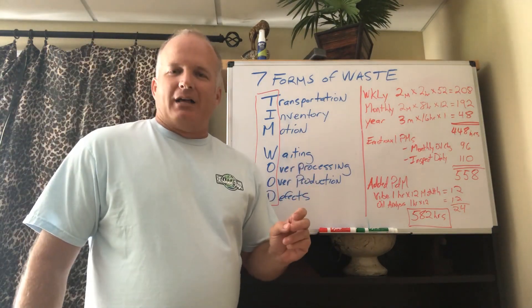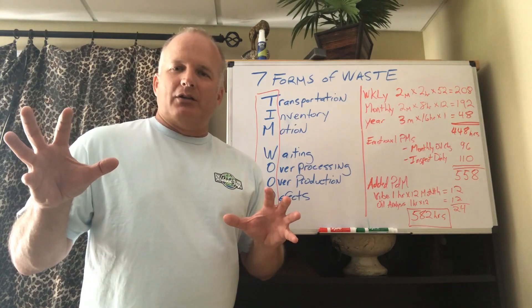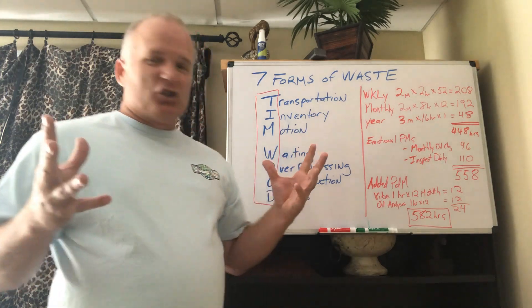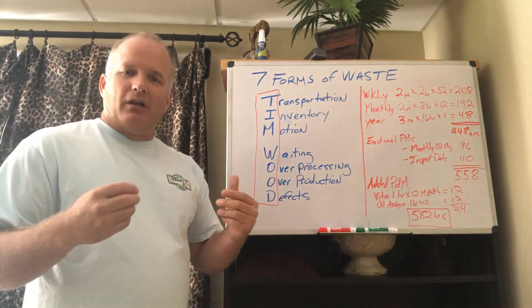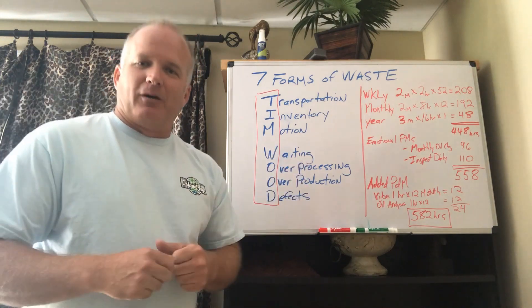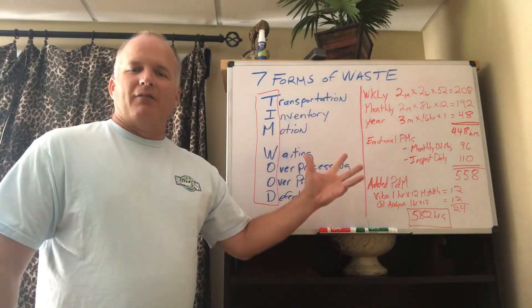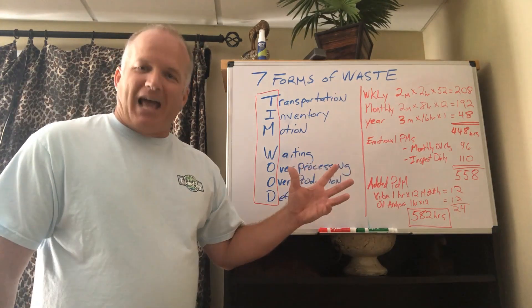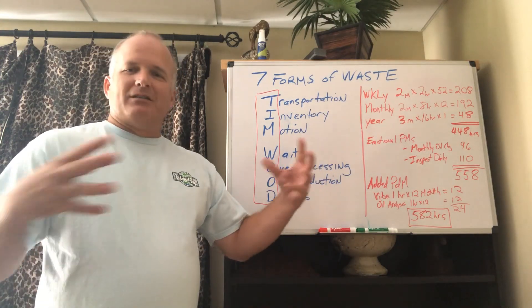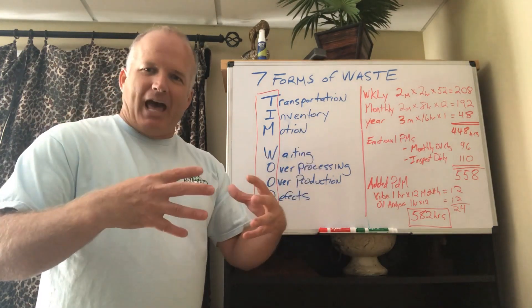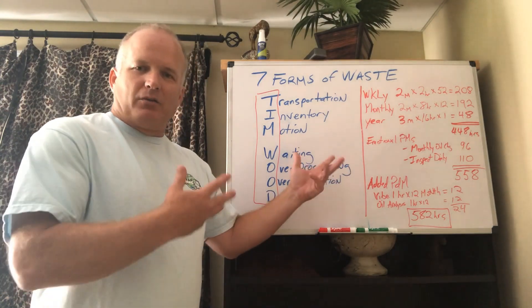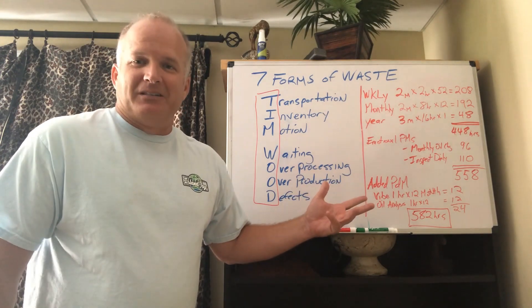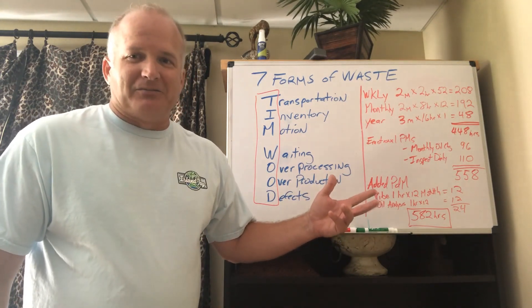What's important to recognize is we added PDM or condition monitoring to time-based maintenance and never integrated them. The textbook will tell you to do an FMEA on this asset, but the problem is at my plant we had close to 10,000 assets. To organize people and data for an FMEA, you'd invest two and a half days per asset — maybe one asset per week, best case. Do the math times 10,000: you don't have that many years.